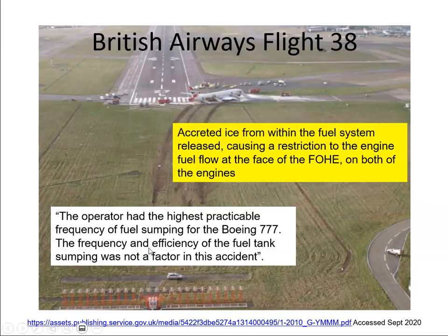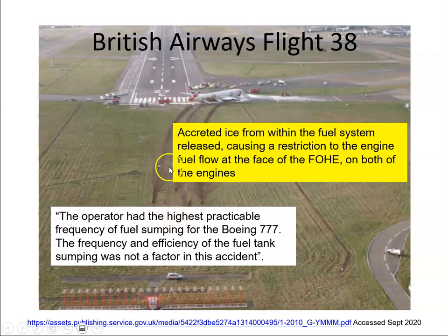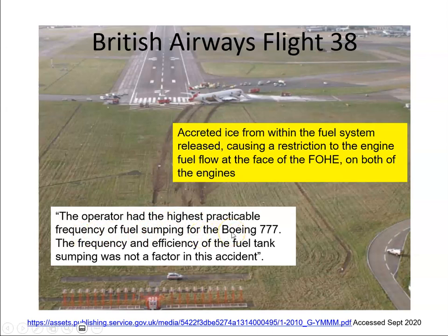An example would be British Airways Flight 38. The Air Accident Investigation Branch report had a probable cause of accreted ice from within the fuel system releasing and causing a restriction to the engine fuel flow at the face of the fuel-oil heat exchanger on both engines. The engines shut down, the aircraft had to glide, and it just didn't make the runway. This is despite the operator having a very good maintenance regime and the highest practicable frequency of fuel sumping for the Boeing 777. It just shows what can happen.